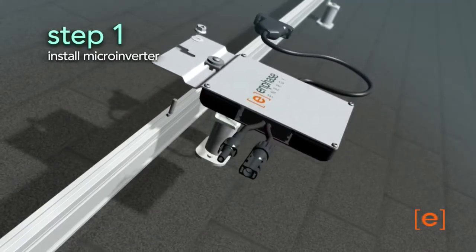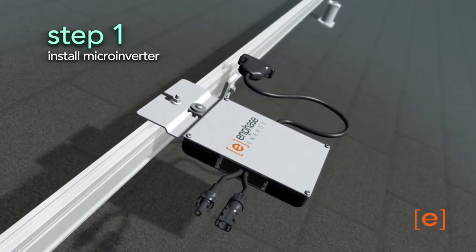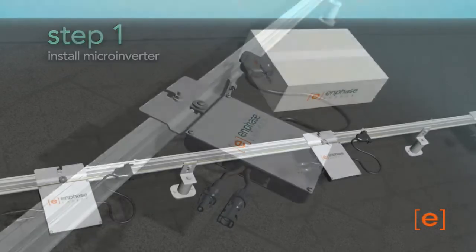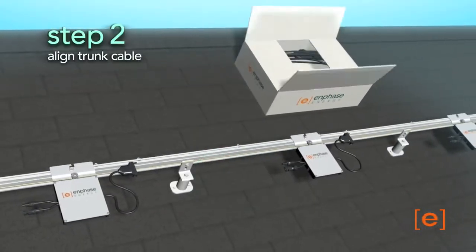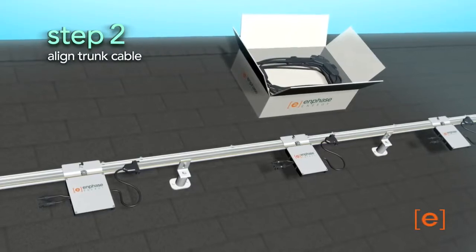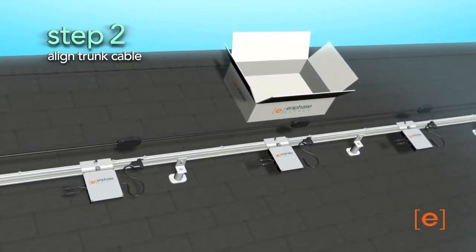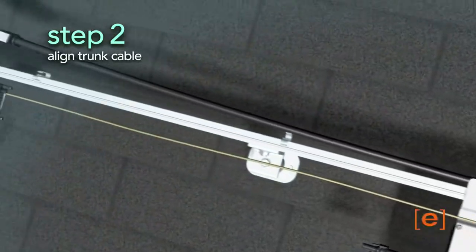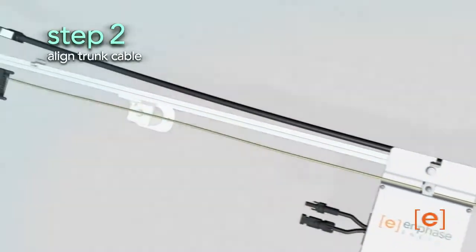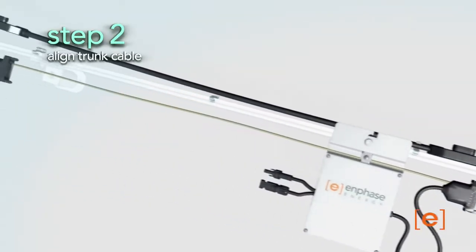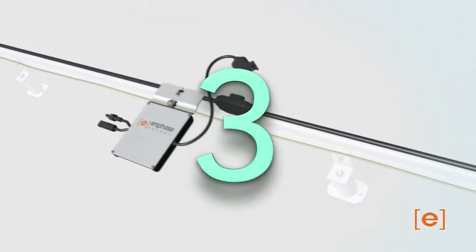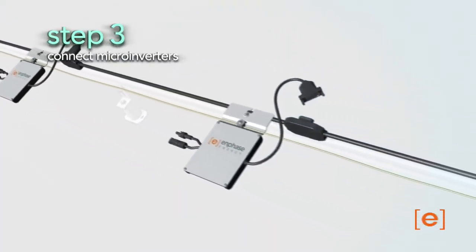First, install the microinverters in the appropriate locations on the racking. Next, lay out the trunk cable in the location required, with the trunk connectors aligned to the location of the microinverters. The cable can be placed on either side of the racking and may be secured with tie wraps or clips. Now connect the microinverters to the trunk cable.